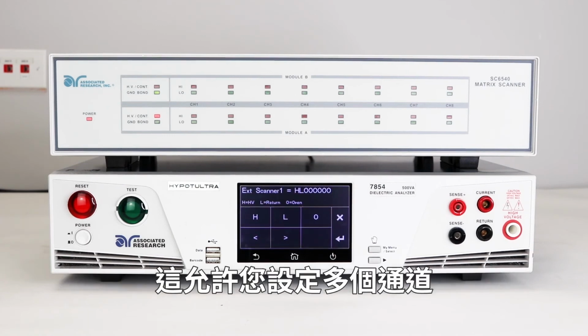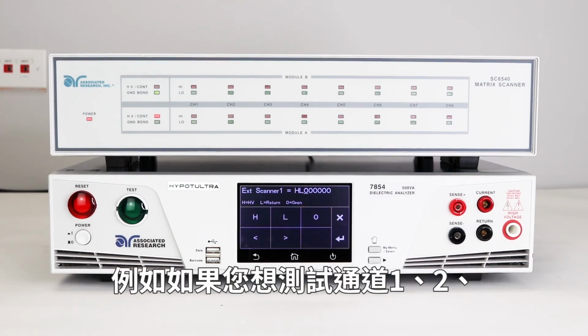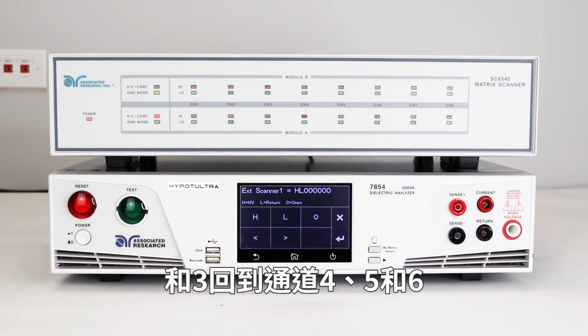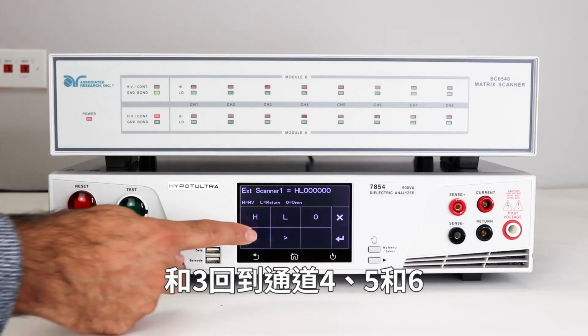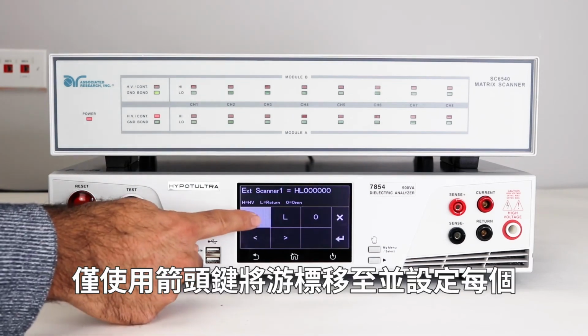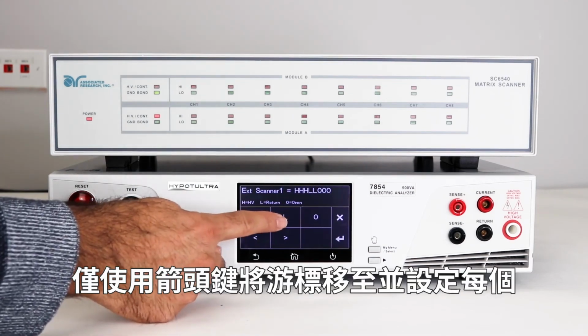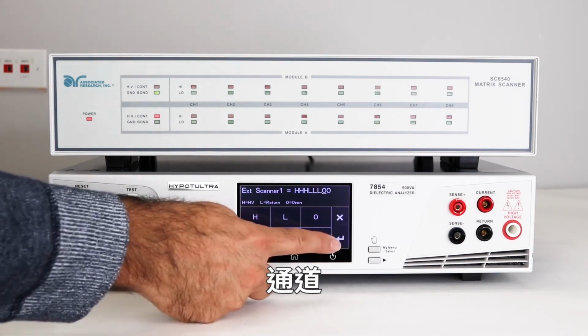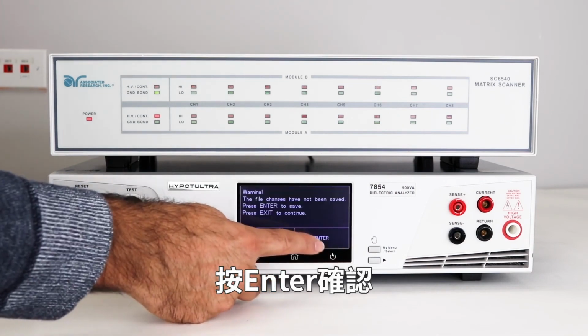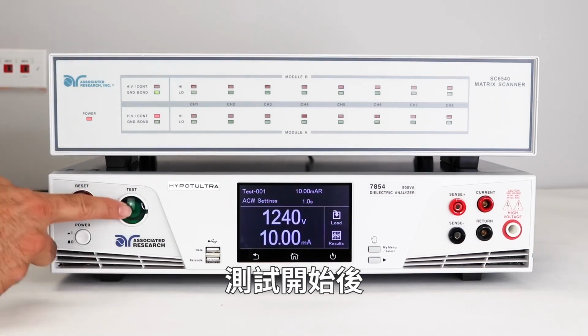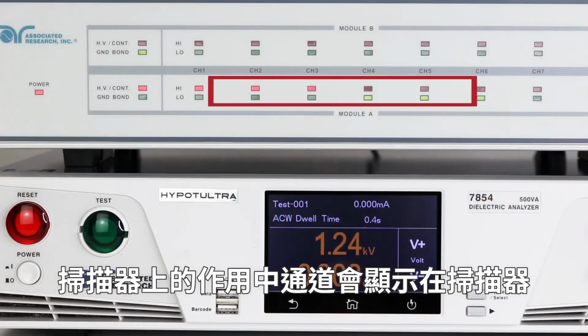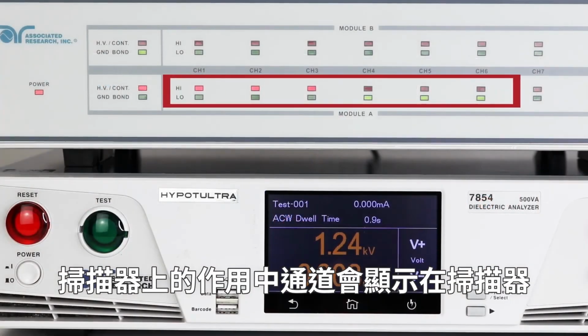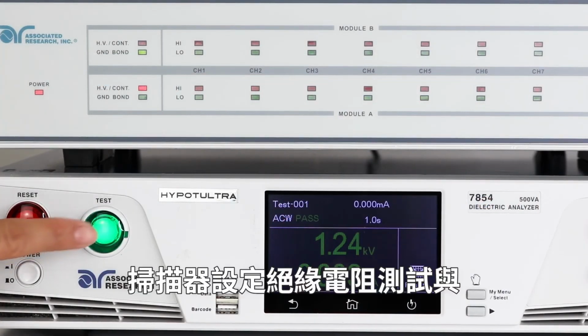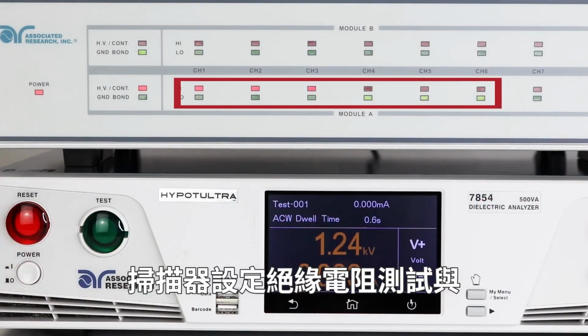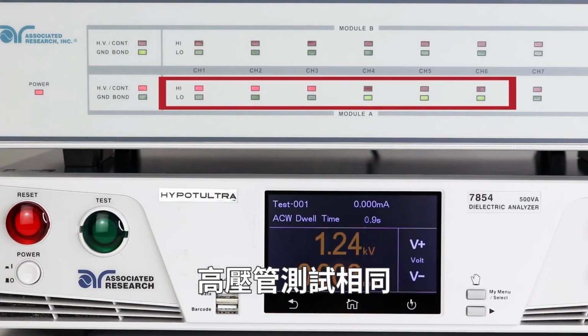This allows you to set multiple channels. For example, if you wanted to test channels 1, 2, and 3, back to channels 4, 5, and 6, simply use the arrow key to scroll over and set each channel. Press Enter to confirm. Once the test is started, the active channels are indicated on the front of the scanner. The scanner, set up for an insulation resistance test, works the same as a HypotULTRA test.